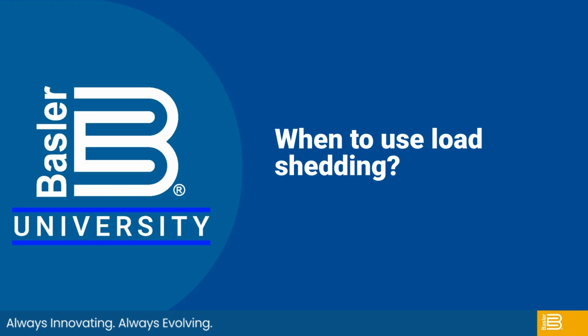And if for some reason you have to take one of those 5 offline, then basically it would transfer what people will call the lowest priority load. So it could typically be something that's not a life critical situation. It could be something that's backed up by the UPS already, or it could be outlets that don't need to be life safety, etc. So hopefully that answers your question.